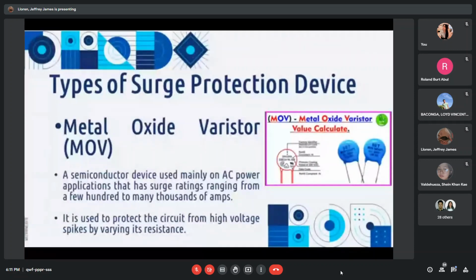Moving on to the types of surge protection device. The first type of SPD is the metal oxide varistor, or MOV. It is a semiconductor device, usually used in AC power applications, that has surge ratings ranging from a few hundred to many thousands of amps. It is used to protect the circuit from high voltage spikes by varying its resistance.